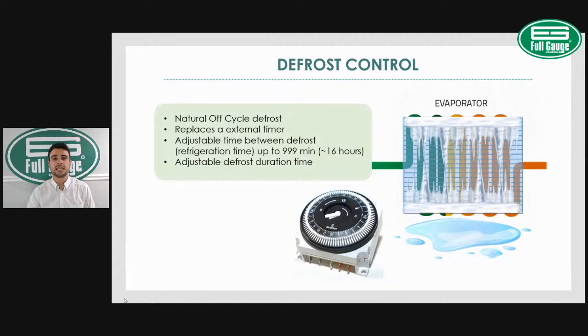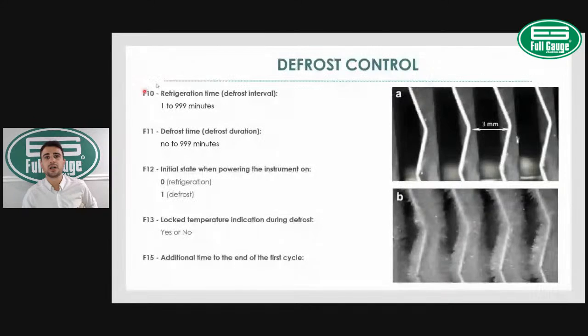So first of all, the first defrost parameter we're going to be looking at is F10. That's the refrigeration time, which is the defrost interval. So let's say we set this to 240 minutes. That means I will have one defrost cycle every 4 hours. If I set F10 to 360, I will have one defrost cycle every 6 hours.